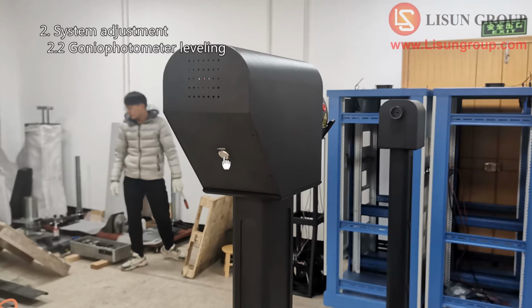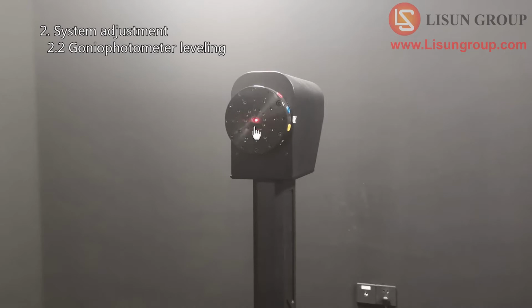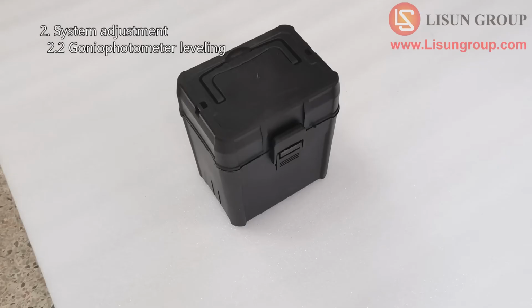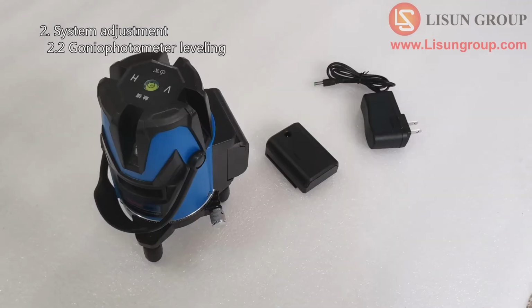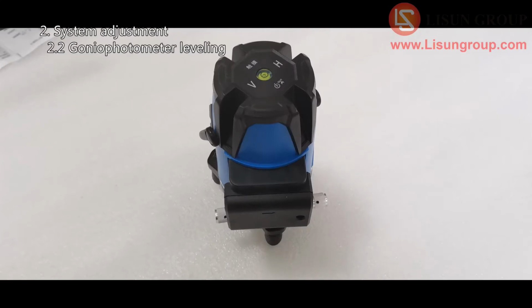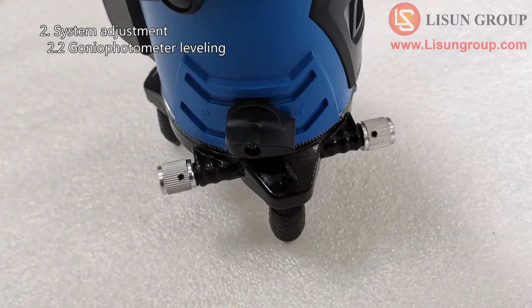There is the switch for the laser on the back of the main arm. Turn it on. Then you can see one laser coming out in front of the main arm. There is a cross laser device inside of this box. Take out the cross laser and its battery. Load the battery into the device. Turn this switch to unlock position. Then the cross laser will be turned on.